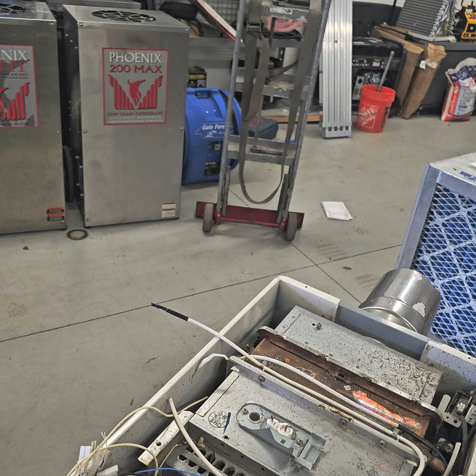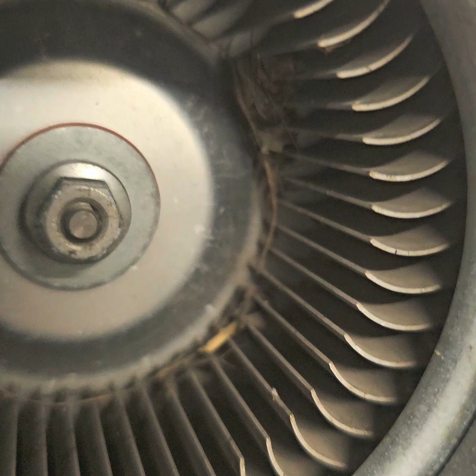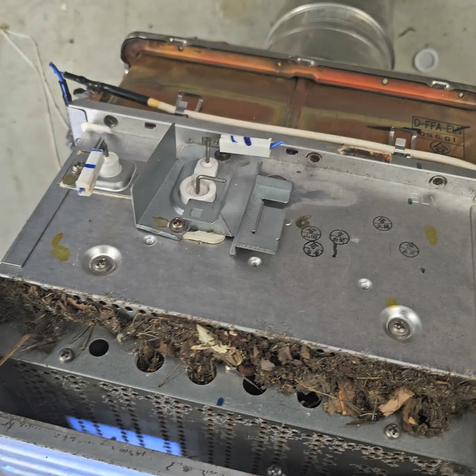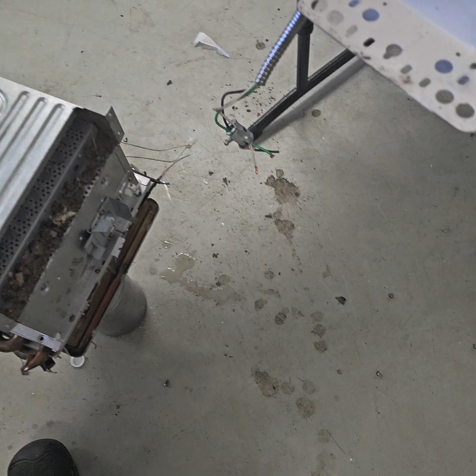We pulled this fan motor out, and if you notice on the inside of here, the amount of heavy debris and everything else on the fan shroud, things of that nature. If you look inside of here, if it were spinning, you'd see it a little bit more clearly. But what I wanted to show you is inside of this portion. Right now, typically your system would look like this if it's in the upright position, but now we have it upside down. We have our fan off, so this is the bottom of the unit, and you can see the amount of heavy debris that's inside of there. Unfortunately, even when we do high pressure nitrogen cleaning, we cannot always get all of that out. So that just gives you somewhat of an idea of what we're dealing with.